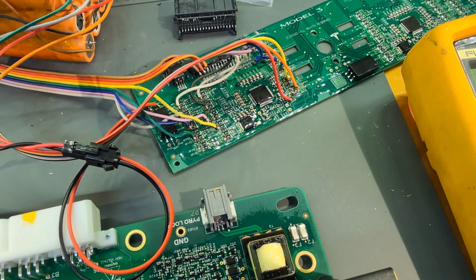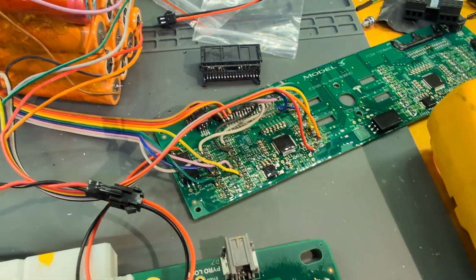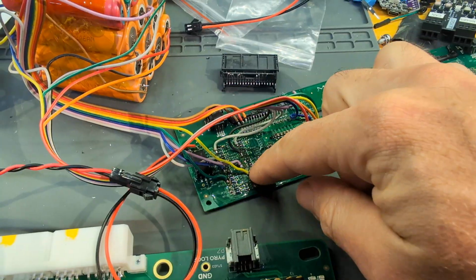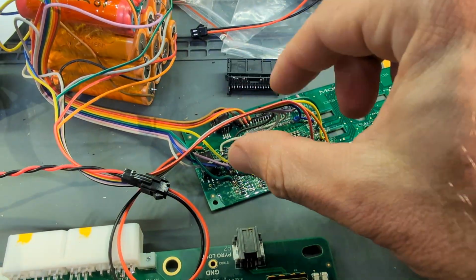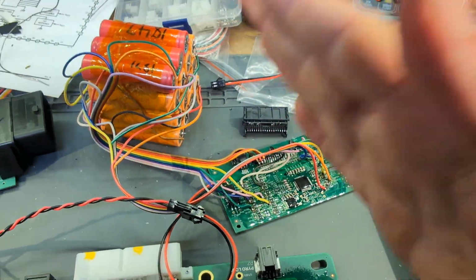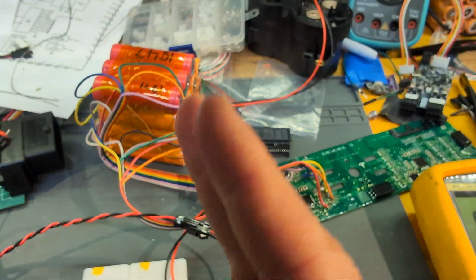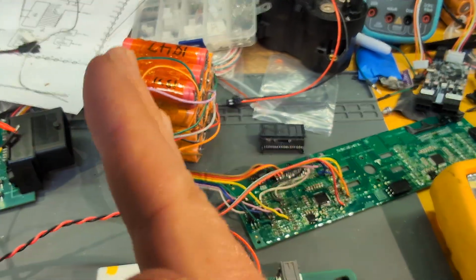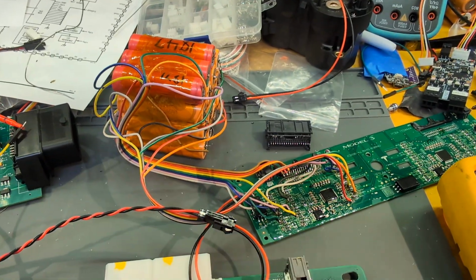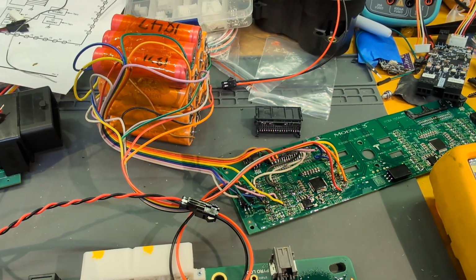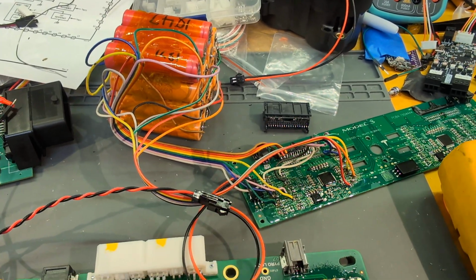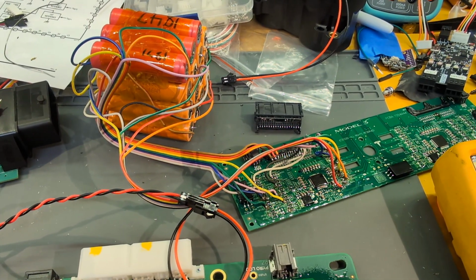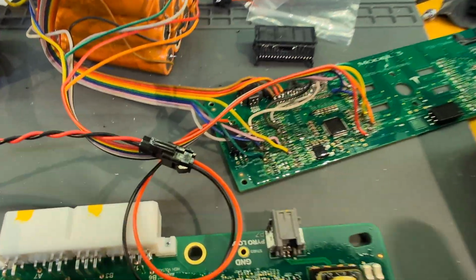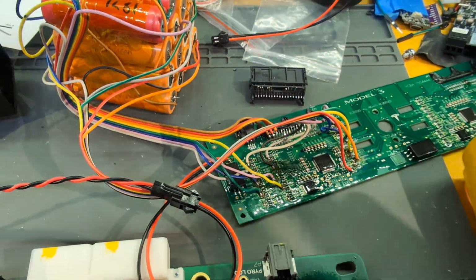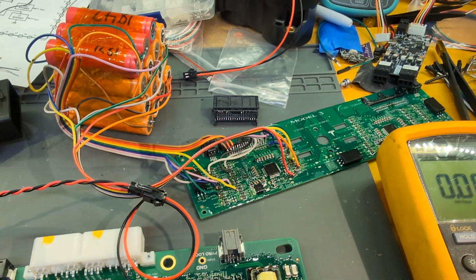Because the way the cells are all in series and the way these things work, you're actually using two of these sets of resistors to discharge one cell, and then you're discharging them in an alternate pattern, like even odd, and then it switches after 1 second and discharges the other even or odd set through, you know, similar resistors, but in the opposite direction. Actually, the current reverses through these resistors. It's not charging the batteries, it's just going the opposite direction through the resistors.